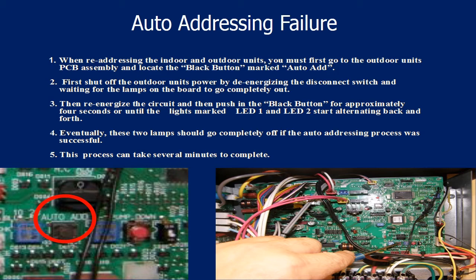First, power off the outdoor unit and wait for all the LED lamps on the main control board to go off. Once the lights are off, restore the power back to the unit. Next, you will have to locate the black button labeled as A.ADD on the board. This button can be found in the lower right-hand corner of the board. Press and hold the button in for 7 to 8 seconds and then release. The LEDs 1 and 2 should now be alternating back and forth. Once the outdoor unit has established communications with the indoor unit, these 2 LEDs will go completely out. This procedure can take up to several minutes to complete.